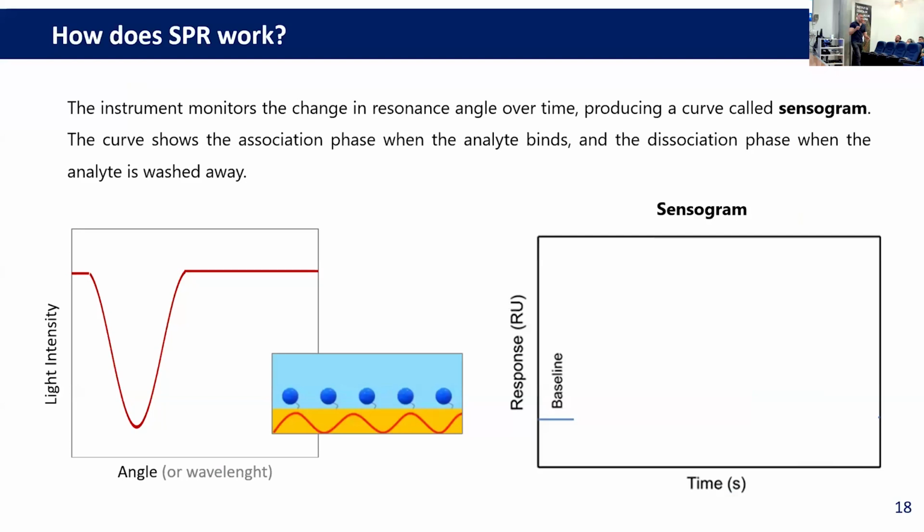So, in order to extract the information from the SPR, we need to build what is called a sensogram. Okay, so we have said that we might have our ligands bound, covalently bound, for example, to our gold surface, and for some angle, we're going to have the production of these plasmons, and then this angle, the angle at which the plasmon is being formed, is proportional, we said, to the mass attached to these ligands. Okay, and through an internal calibration of the equipment, every company that has SPR has their own calibration. This is directly proportional to a magnitude that they call response units for the SPR.